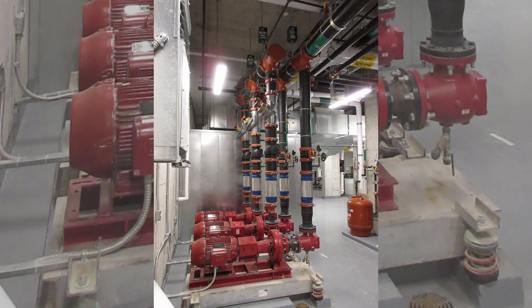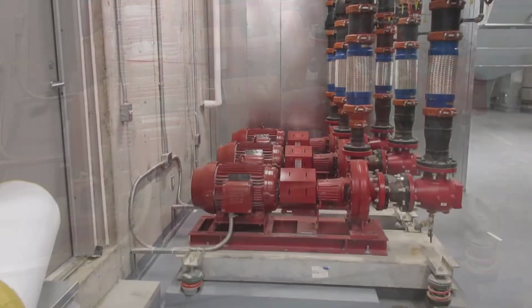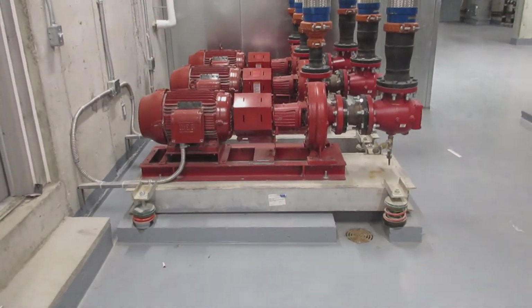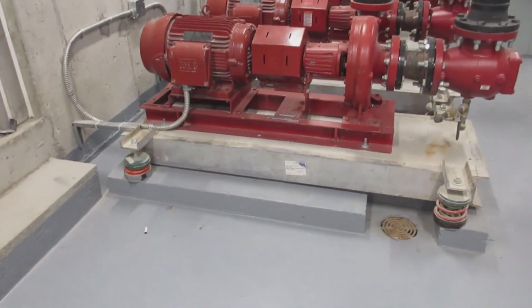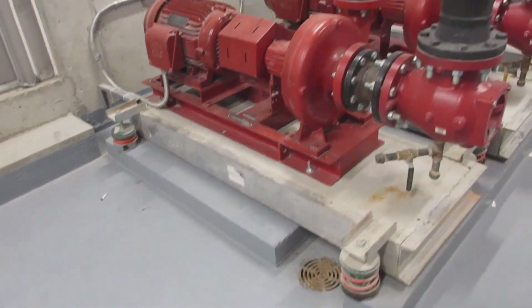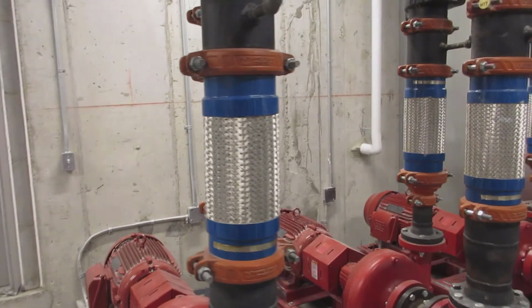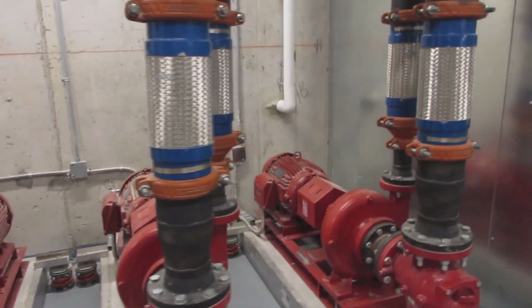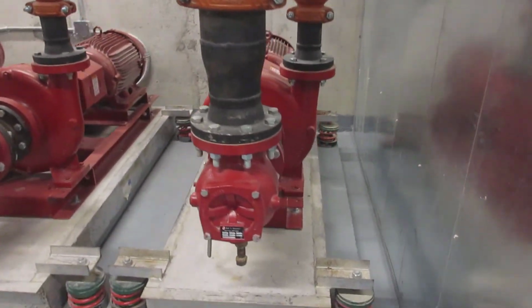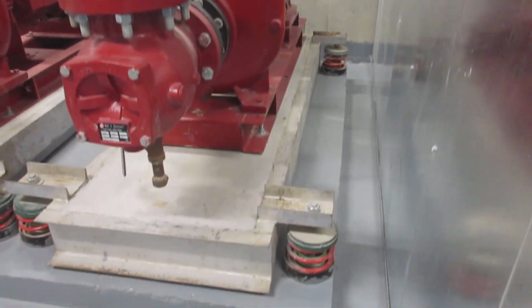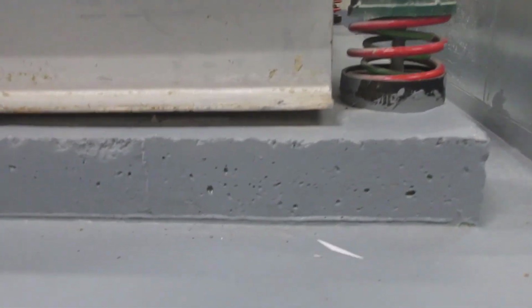This picture shows the 3 chilled water end suction pumps, all mounted on spring-supported inertia bases and connected to spring hanger-supported piping with flexible metal hose connectors. The first thing I notice is the creative coordination for the floor drain location, and how the housekeeping pads appear to be slightly undersized for the isolators. These flexible metal hose connectors are ineffective for vibration isolation, but can help with reducing pipe stresses. The isolators here appear okay, but the inertia bases are installed closer than 2 inches to the housekeeping pad surface, and there appears to be some debris under them.